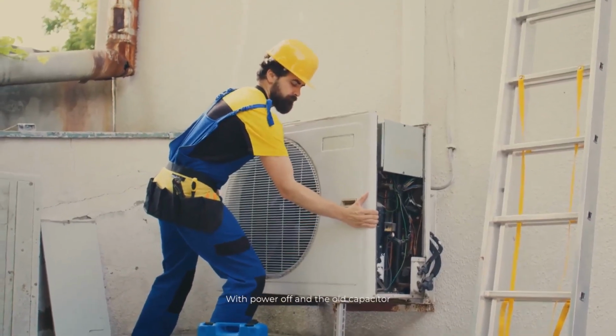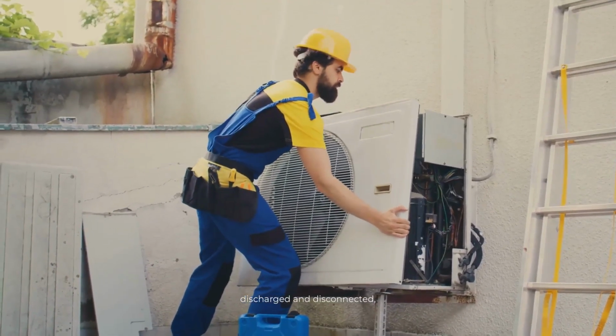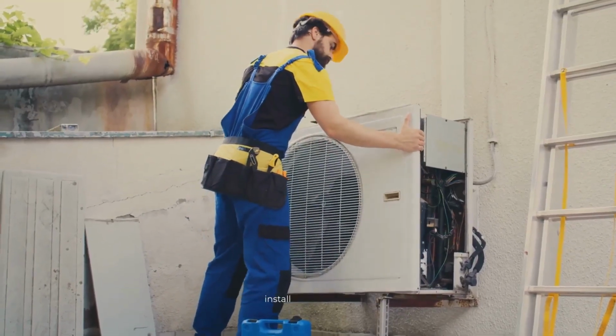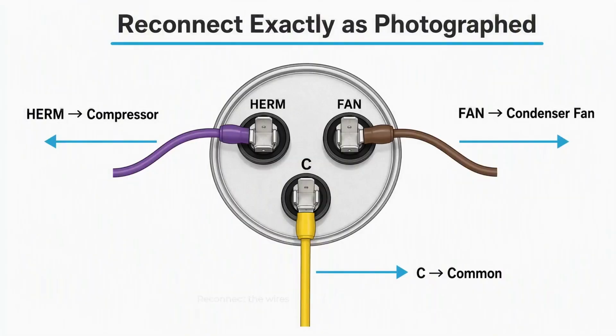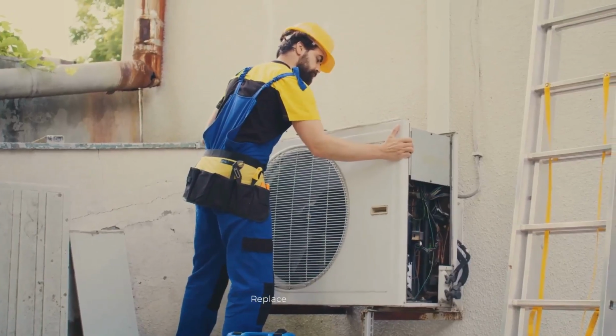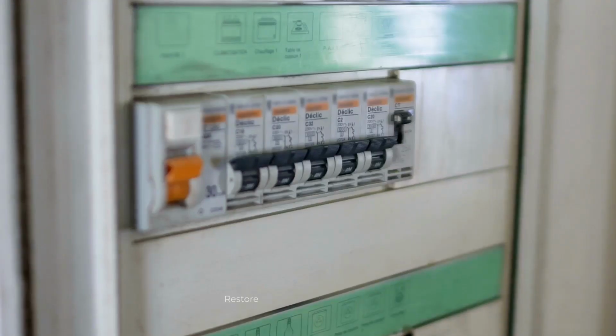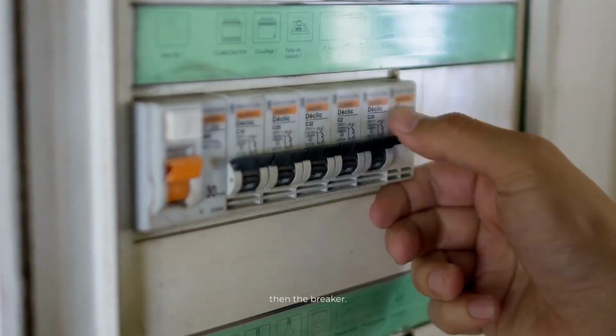With power off and the old capacitor discharged and disconnected, remove it from the mounting bracket and install the new one. Reconnect the wires exactly as your photo shows. HERM to HERM, fan to fan, C to C. Replace the access panel. Restore power at the disconnect first, then the breaker.